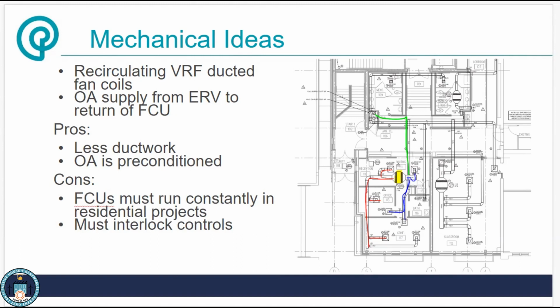I went through a couple of our projects and pulled out some mechanical designs that were either really good, interesting, or stuff we very commonly see. On screen now is a non-residential project with a recirculating VRF fan coil: one central outdoor unit running a bunch of smaller indoor fan coils recirculating within their spaces, plus a centralized ERV, shown as the green line, ducted right into the return of that fan coil. We've seen this as a way to save on ductwork by combining the two.